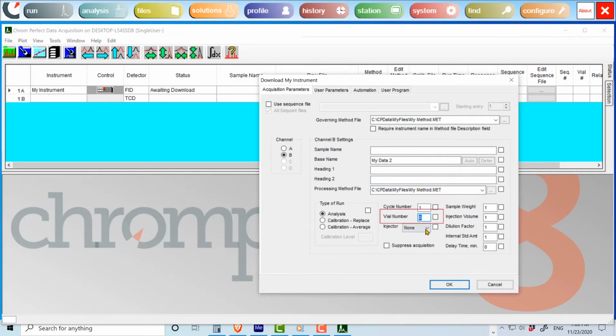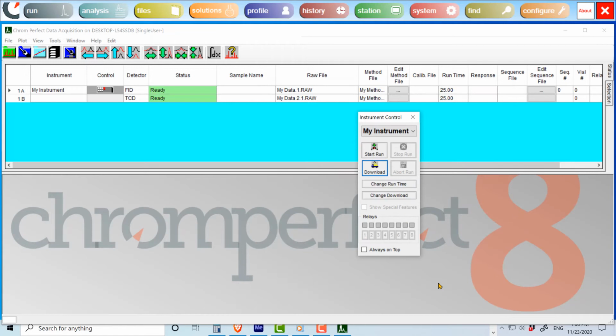If you are using an autosampler, set the vial number. If you are using a 7890 with an autosampler, set the injector to ALS. Before we leave this form, see that type of run is currently set to Analysis. Later, when we have built our calibration file, we will discuss how standards can be run and the calibration updated automatically. The options are Calibration Replace, to replace the responses in the calibration file with new data, or Calibration Average, to average the new results with the existing responses. As you select either of these calibration update options, the calibration level field becomes available. We will cover these calibration options later, so for now, keep the checkbox set to Analysis.